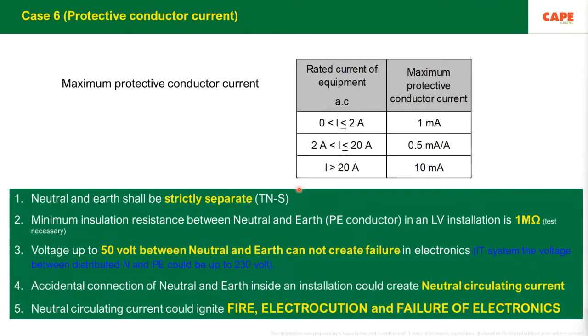In one incident, at one top leading company, somebody called me saying my battery rack is creating sparks. What could be the reason? Then very easily we could find out that it was due to a leakage current. They were using a device called, again a black box, I forget, a digital earthing system. This device says that you don't need to earth your electrical apparatus, and that system was creating a hell of a lot of leakage current, and this was the reason for the arc.